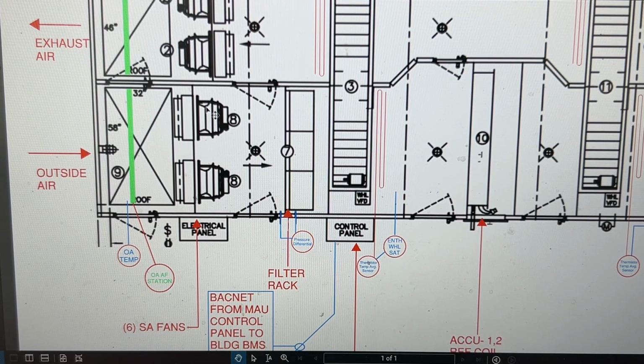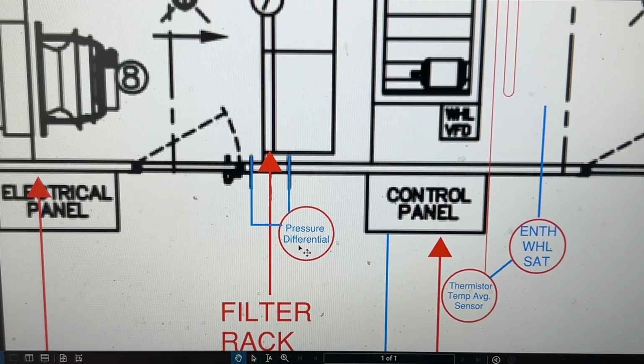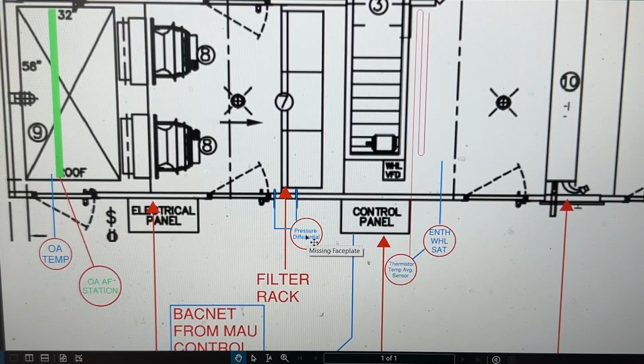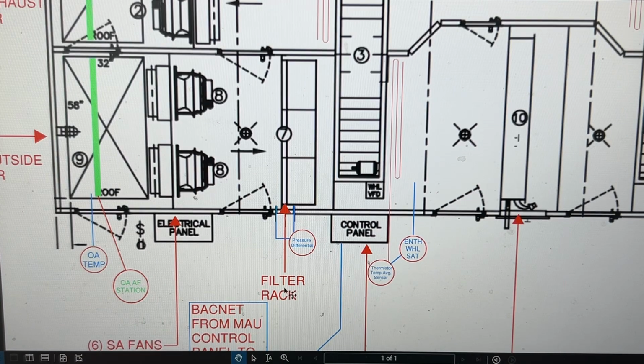Right here, we've got a bank of 6 supply air fans that are drawing that outside air in, and then they're pushing it through this filter rack. So we've got a differential pressure here. We've got a Magnehelic glass gauge on the side for a visual reading as you're standing in front of the air handling unit. We also have a static pressure sensor as well. Basically it'll have poly tubing on the inlet side of that filter bank and on the outlet side of the filter bank, so that it notifies us when we have a big difference between the two, when these filters are plugged up and have to be replaced.